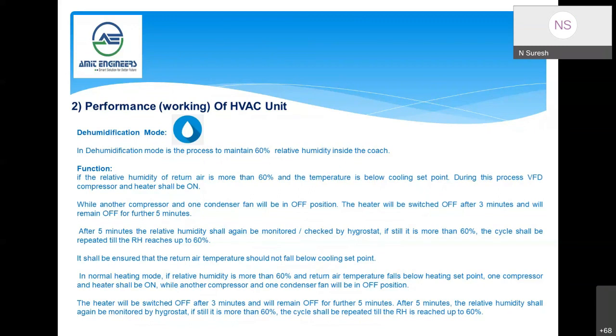To avoid that, a system logic is implemented here, and it is well proven even in other LHB coaches. There, simultaneously one heater and one compressor will be on, and the dehumidification also will happen. Once the RH of 60% is achieved, the heaters will switch off, and the compressor also will run for a few minutes and then switch off. So that is how the dehumidification mode functions here.